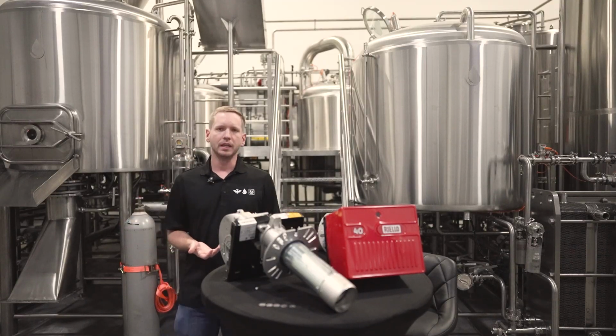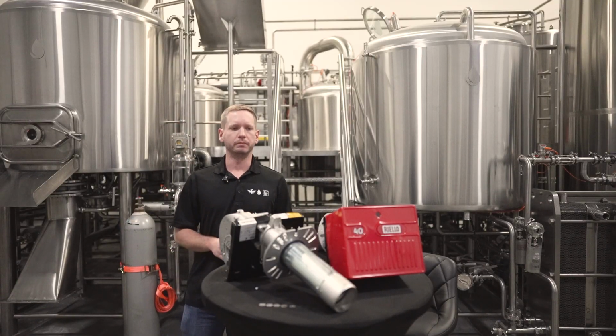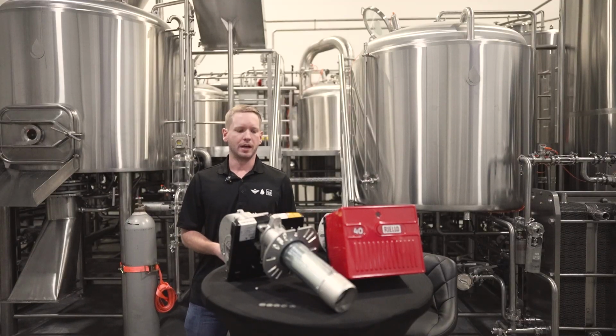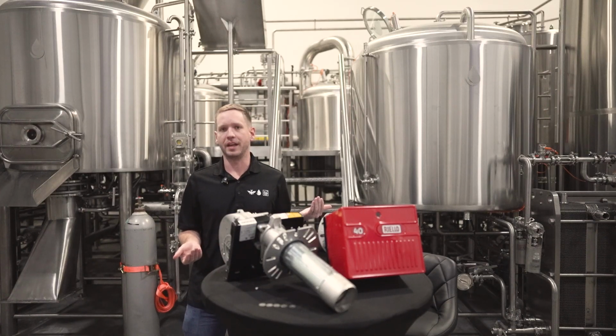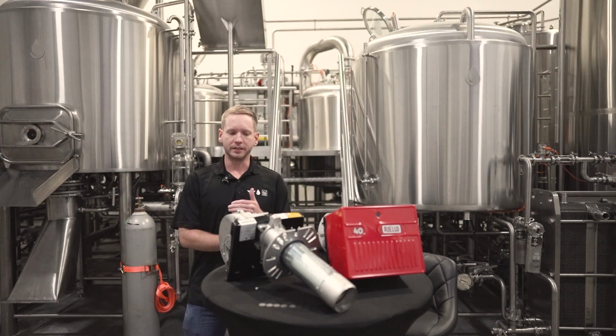For continued maintenance cycles, it's worth giving these a quick look over every 6 months, and then really digging into the bones of it annually, and making sure that your burner tech is coming out annually just to make sure that everything is operating the way it should. As I mentioned at the top, these machines are incredibly hardy. They really don't fail all that often if properly maintained. They're very simple. However, like most things in a household or any brewery, if they are not maintained, they will fail. It's not an if, but a when. So proper burner maintenance is super important for any direct fire system.